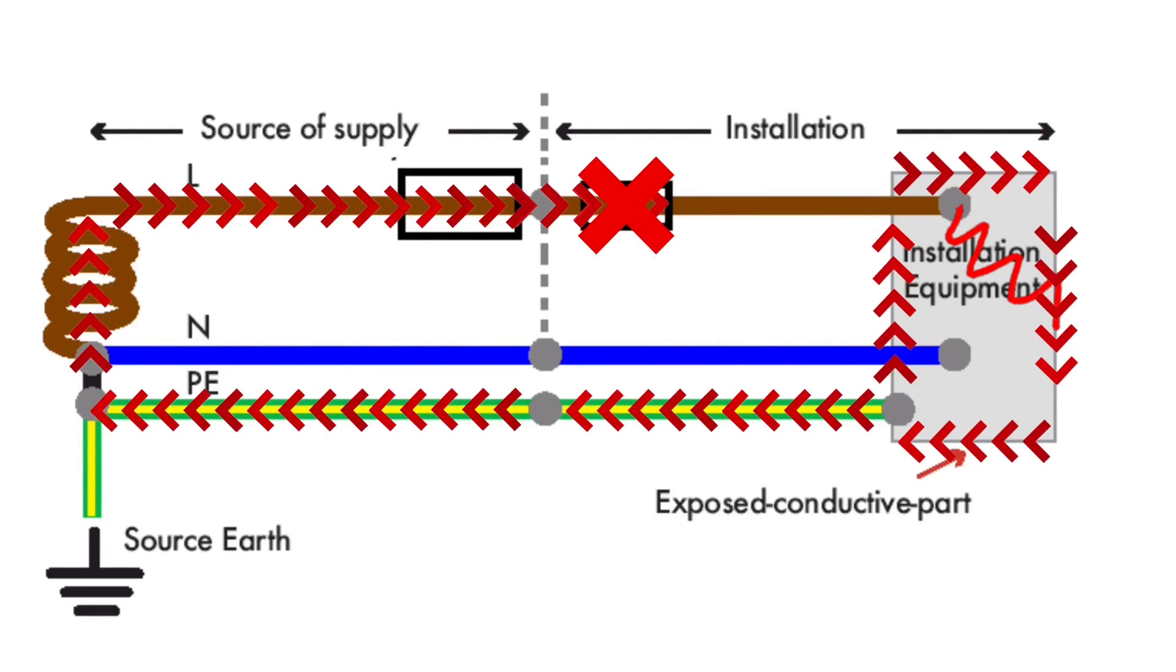This is the full earth fault loop path and needs to be a very low impedance in order to generate a very high fault current to cause rapid operation of the over current protection device.